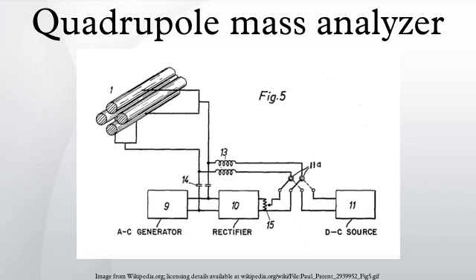In a quadrupole mass spectrometer, the quadrupole is the component responsible for filtering sample ions based on their mass-to-charge ratio. Ions are separated based on the stability of their trajectories in the oscillating electric fields that are applied to the rods.